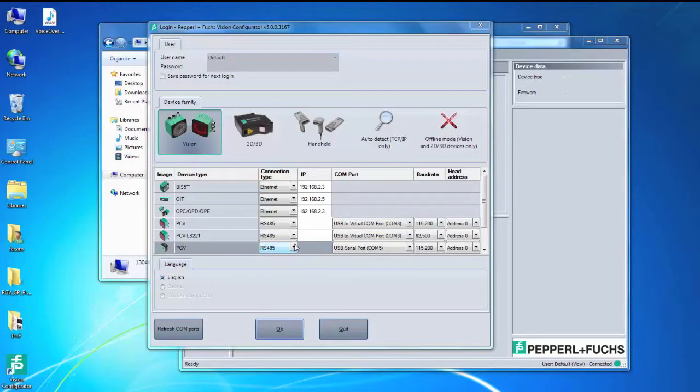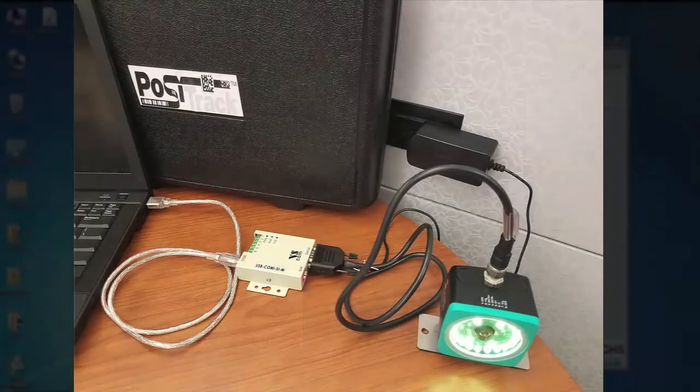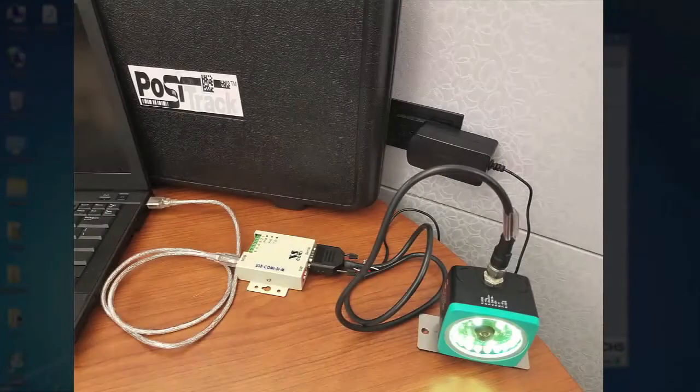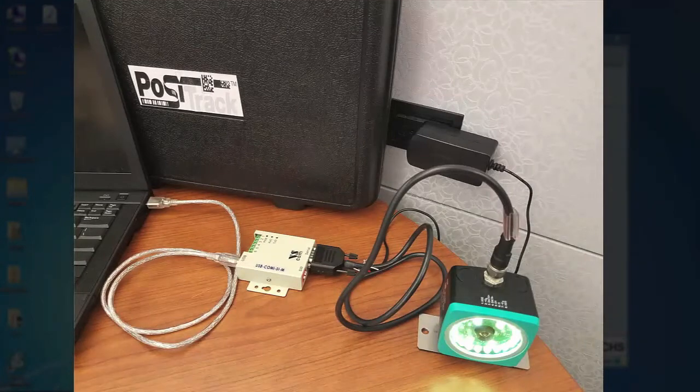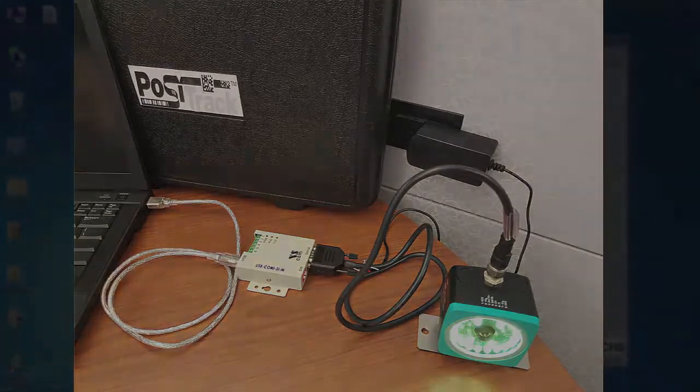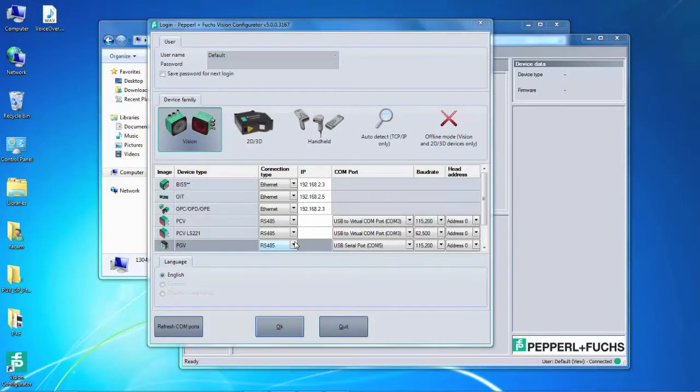This is a good time to physically connect the PGV read head to the RS-485 converter. The converter is what we use to pair the read head to the PC. You want the connection to look like this. The V19 cable connects to the connector on the read head. The USB coming from the converter will connect to a USB port on your PC and the power supply to a standard wall outlet. Once you connect the USB to the PC, you will see Windows begin to install the USB device driver. After a few seconds, you will see a prompt telling you the driver software was successfully installed.